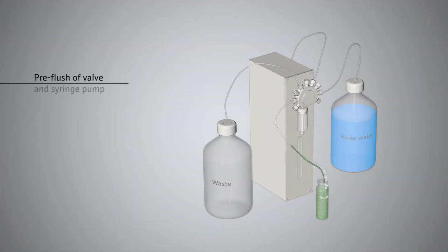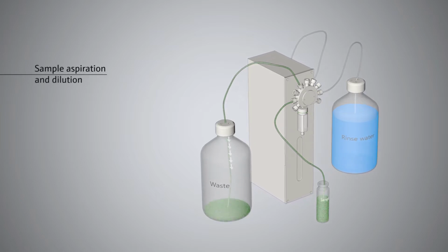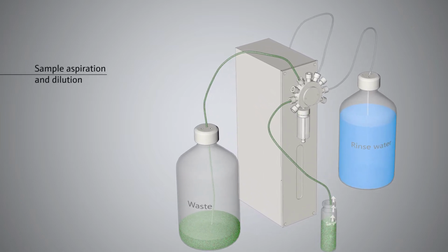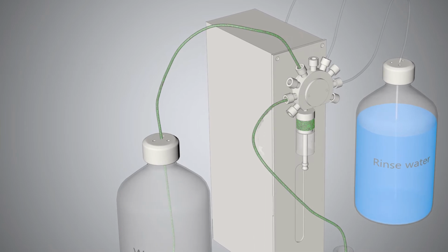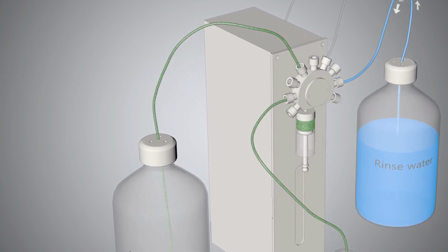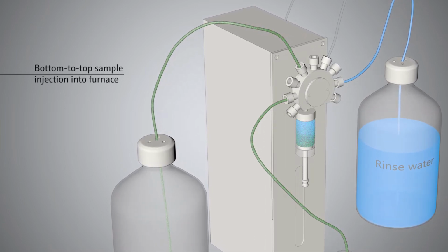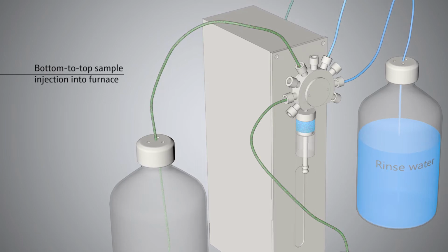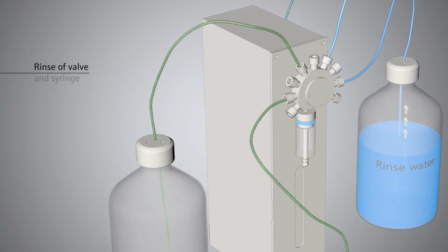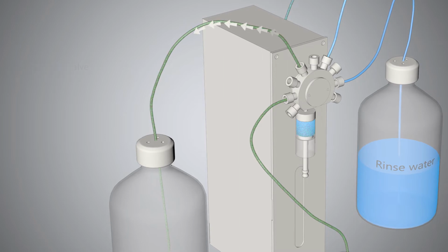Most TOC and TNB analyzers have thin tubes, and the sample is aspirated directly into the syringe pump, leading to particle sedimentation and material wear. Sample dilution is necessary to avoid overloading the detector or exceeding the calibration range. There is no reverse rinse after injection, thus remaining particles in the syringe lead to carryover, false results, and wear.